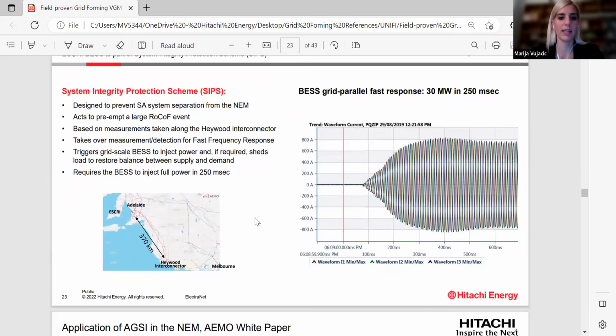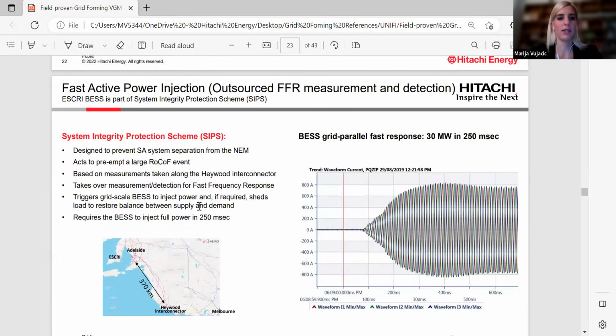Together with ElectraNet, we designed a system integrity protection scheme, which was designed to prevent South Australian system separation from the national electricity market. So a main requirement for BESS was to respond with 80% of the nominal power within 250 millisecond time upon receiving the trigger signal, and this was successfully demonstrated, as you can see here.